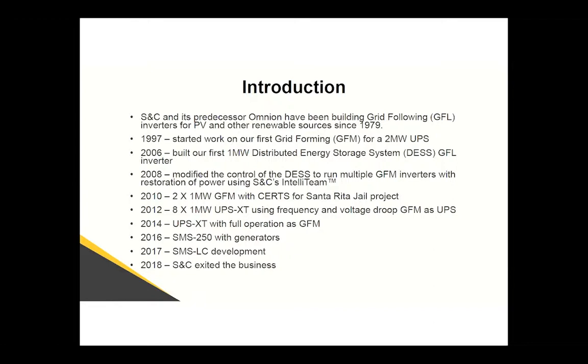In 2006, we started working on a distributed energy storage system with AEP that we eventually renamed a storage management system. 2008, we modified the grid following to be a grid forming inverter. In 2010, we started working with the CERTS algorithm for the Santa Rita Jail project. In 2012, we're working with a UPS where we started using frequency and voltage droop. In 2014, we went to full-time operation as a grid forming inverter in that UPS.